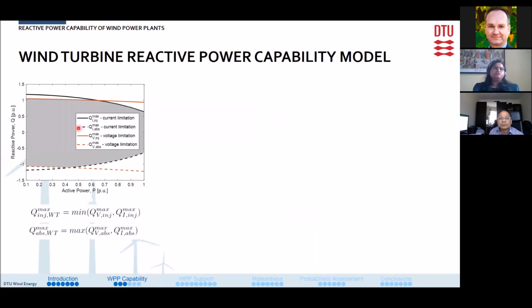So here, to demonstrate the converter voltage limited and converter current limited reactive power, we see that the red curve shows the voltage limited reactive power, while the black one shows the current limited reactive power. At any operating point, the reactive power capability is either voltage dependent or current dependent. And the gray region here is the actual reactive power capability of the wind turbine. So this can be obtained from the equation shown below here.